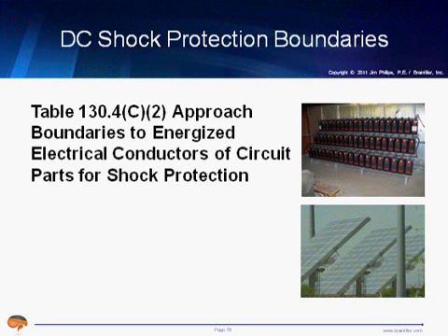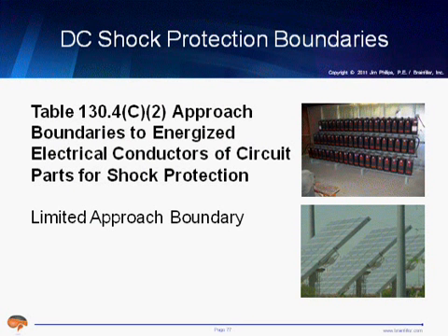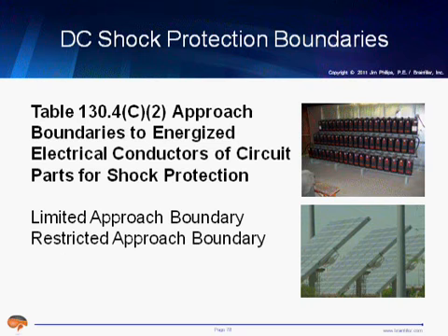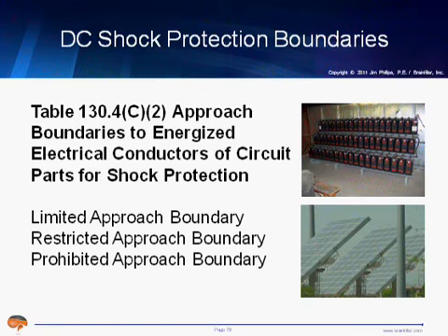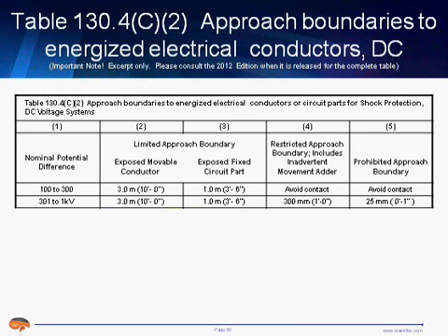DC is making its way into NFPA 70E, and I'm going to talk more about DC later on, but this new table is going to have, much like the AC table, a limited approach boundary and a restricted approach boundary and a prohibited approach boundary. And just an excerpt of the table, a very small excerpt, because you really want to get a copy of the 2012 NFPA 70E. It has everything that you need in there, but just a small excerpt for illustration purposes.